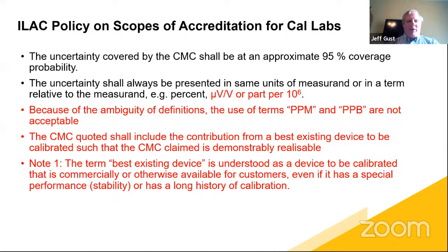So further going on about the policy on scopes for calibration labs. It states that the uncertainty covered by the CMC shall be an approximate 95% coverage probability. I did a talk at the NCSL conference earlier this year about that. When we use the term approximately 95%, what we're saying is 2 sigma. And I just want to clarify that we mean 2 sigma. The reason we don't say that is because the mathematical definition of 2 sigma is 95.45% level of confidence.